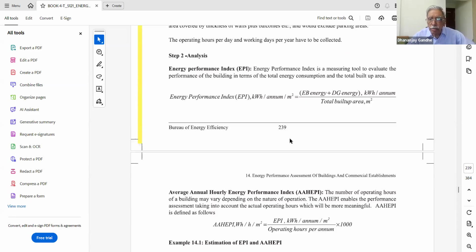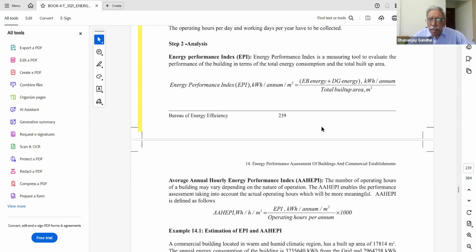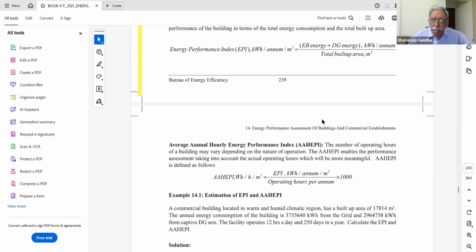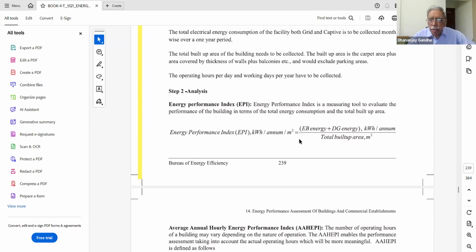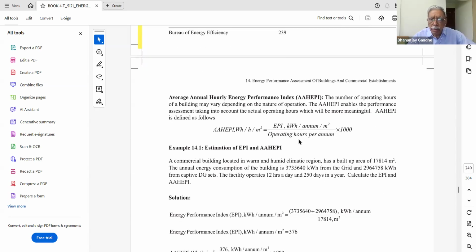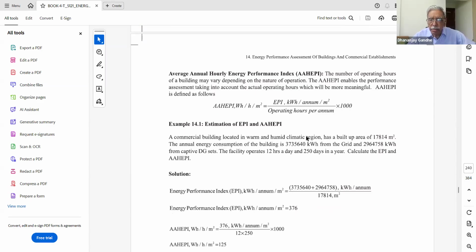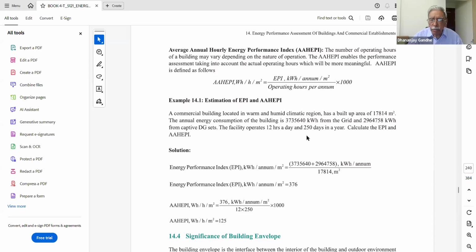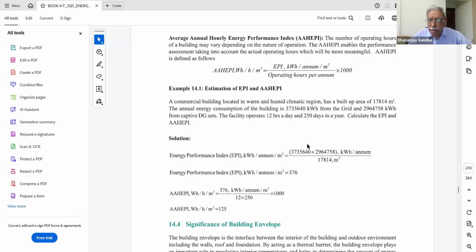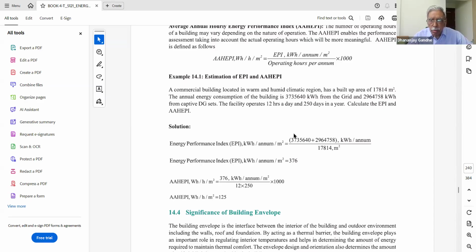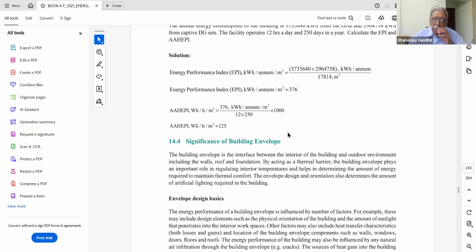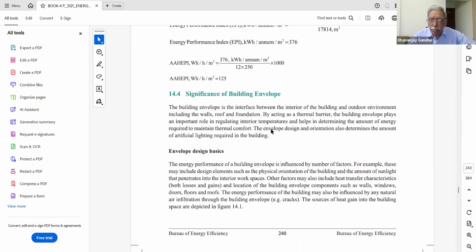The energy performance index is the total sum of electricity consumed per annum divided by the built-up area of the building. This is expressed in kilowatt hours per square meter. The average annual hourly energy performance index, short form AAH EPI, is EPI divided by the number of working hours of that particular building in hours per year. These two indexes are calculated. We have seen the examples of how to calculate these values. The values are 376 and 125. This is what we studied.